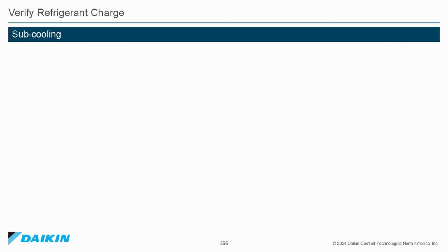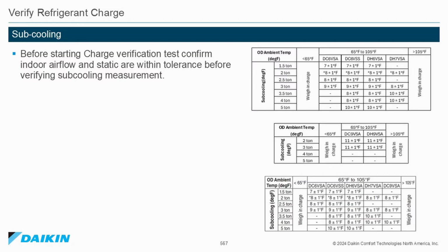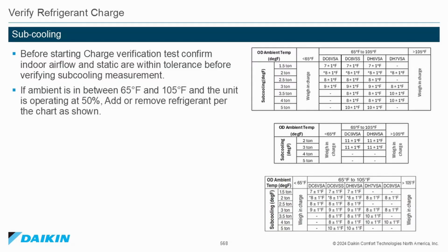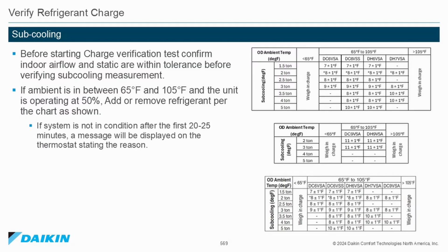Verify refrigerant charge. Subcooling. Before starting charge verification test, confirm the indoor airflow and static pressure are within tolerance before verifying subcooling measurement. If the ambient temperature is between 65 and 105 degrees and the unit is operating at 50%, add or remove refrigerant per the chart as shown. If the system is not in condition after the first 20 to 25 minutes, a message will be displayed on the thermostat stating the reason.